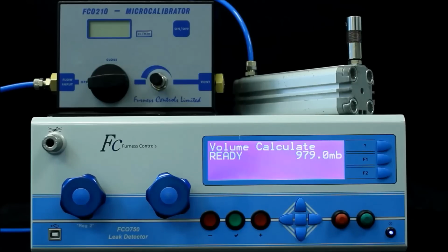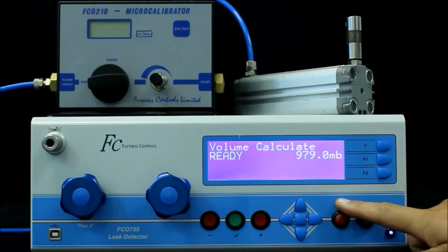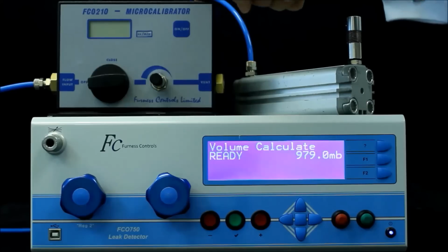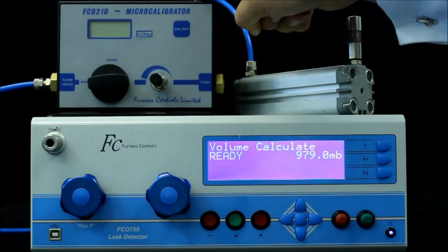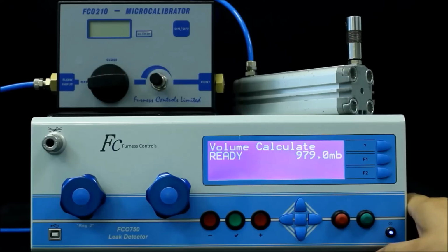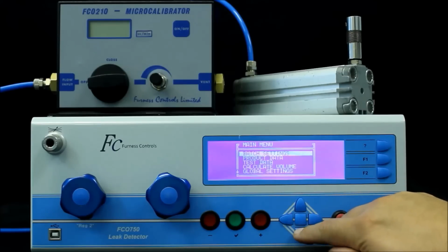This is a short tuition video just to show you how to set up the volume in your test data within the FCO750 leak detector. I have the FCO750 leak detector here, I have a test part here, and I have a FCO210 micro calibrator here.